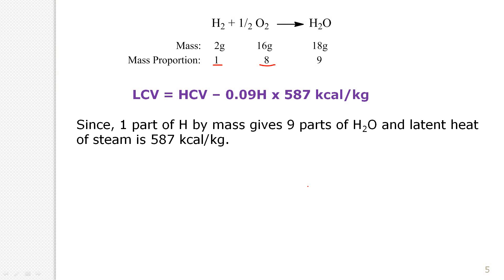Let us do a small exercise. After the HCV calculation, we know the LCV definition: LCV = HCV − latent heat of steam, which we can write as HCV − 0.09H × 587 kilocalories per kg, where H is the percentage of hydrogen present in the fuel. We know that one part of hydrogen by mass gives 9 parts of water, so we subtract that latent heat of steam.